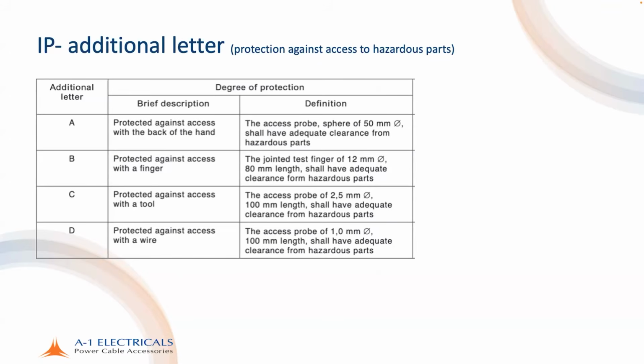See, let me just turn off this background noise. Is it better now? Yeah, much better. So when we have an IP code, there may be up to four alphanumeric characters. The first two are numbers, the second two are letters, but you may have a minimum of two also. The B and the D: firstly, you need to understand when the additional letter comes into the picture at all.